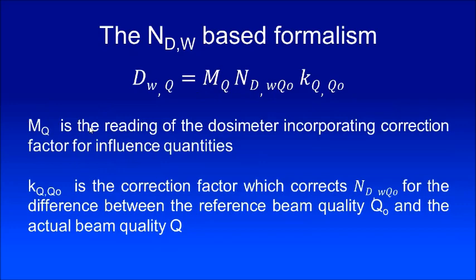M_Q is the reading of the dosimeter with all corrections incorporated for the influence quantities. K_Q,Q0 corrects the N_D,w,Q0 — which was obtained for Cobalt-60 as the reference beam quality Q0 — to the actual user beam quality Q. So the only conversion factor required here is K_Q,Q0.